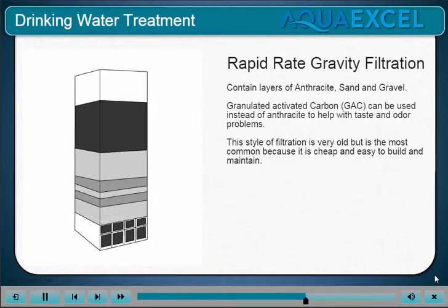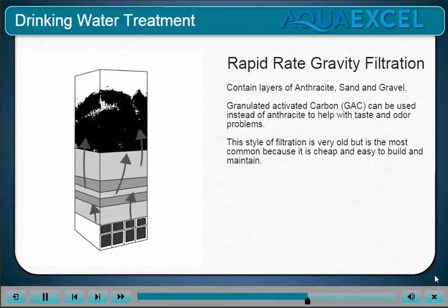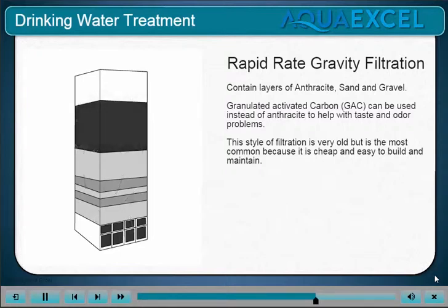Most filters are cleaned by reversing the flow of water through the media inside to suspend it a bit and allow spaces for the collected particles to be washed out. The backwash will contain sludge that can be further treated in a wastewater treatment plant.